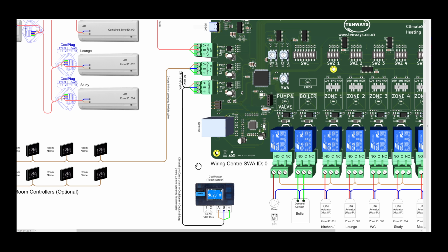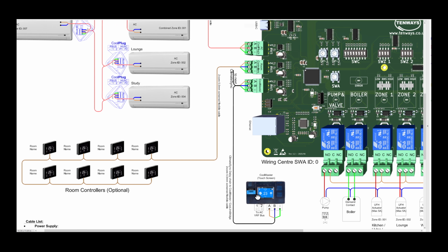If you have a VRF or VRV system, it's always recommended to install a CoolMaster and not a cooling bridge, as you will connect the CoolMaster also to the VRF bus line, which will allow fault finding through the CoolMaster later. So that could be very useful. And also the CoolMaster has a touch screen, which allows some local control from the touch screen on the CoolMaster.